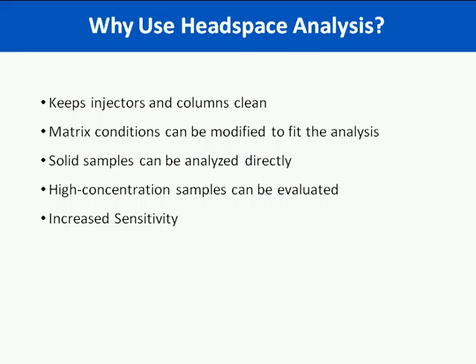Some of you who are new to headspace analysis may have a question as to why you would even want to do headspace. There are many means by which analytes are going to be injected into your GC. Most of your analysis is performed by direct injection with some prior sample preparation. However, this technique may result in dirty injectors and columns due to non-volatile residues that can be injected along with your analytes of interest. Headspace allows you to exclude unwanted materials from your injection because headspace creates a gas phase injection — only the volatile components reach the GC.